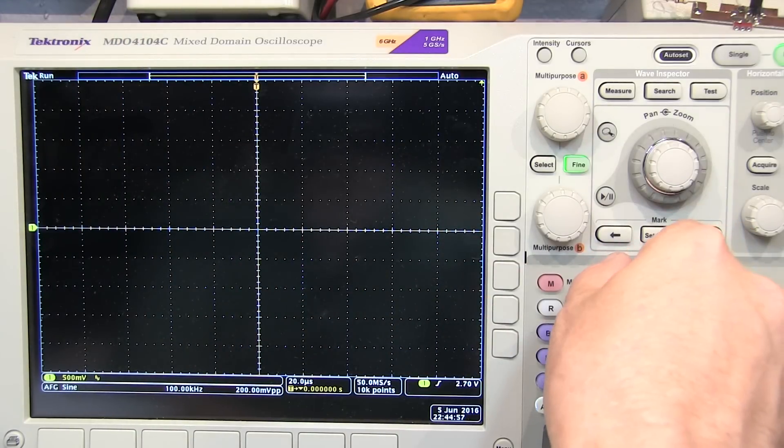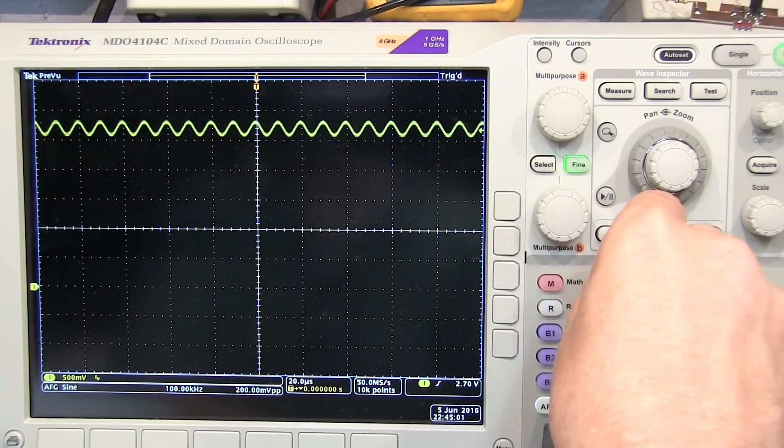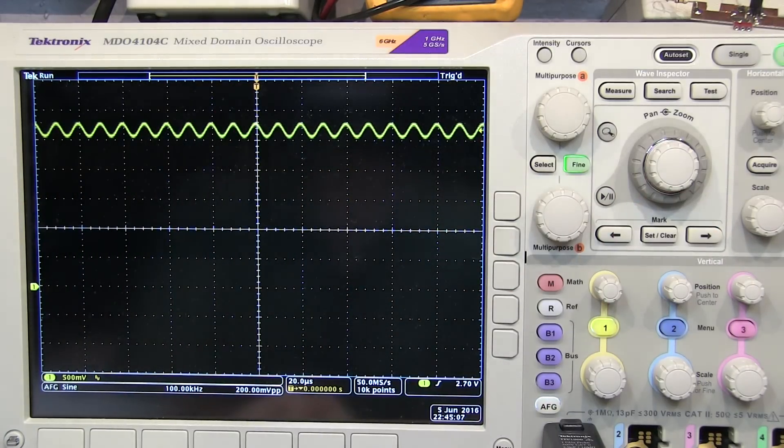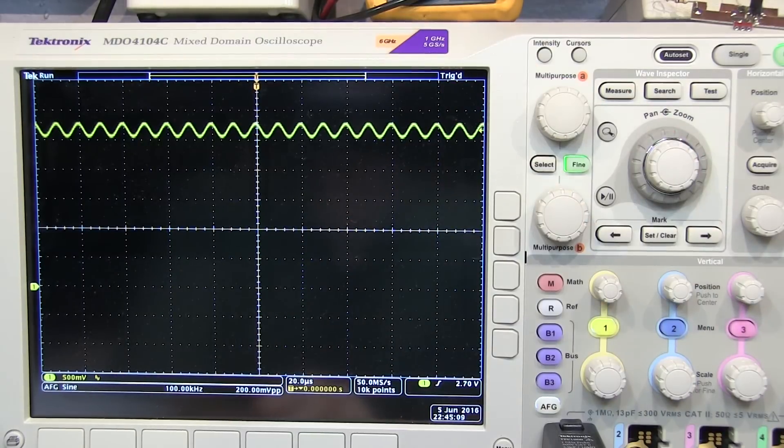So my signal is sitting just above the top of the screen. So I need to move my vertical position control down, so I can bring my signal back on again. So now at 500 millivolts per division, I can now see my signal riding on top of that 2.7 volt bias, and it appears twice as big.